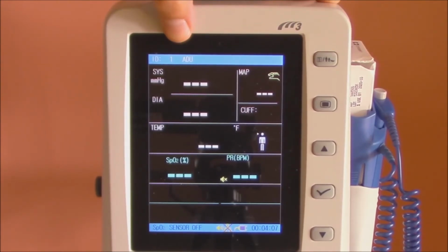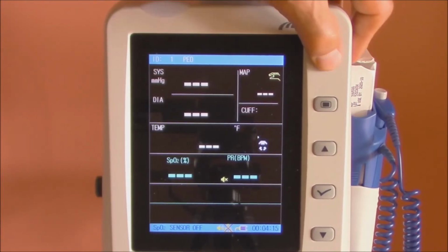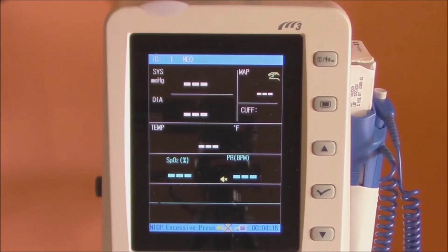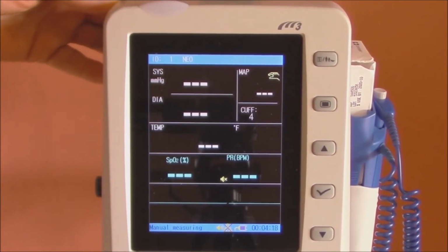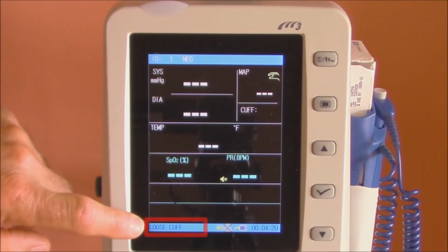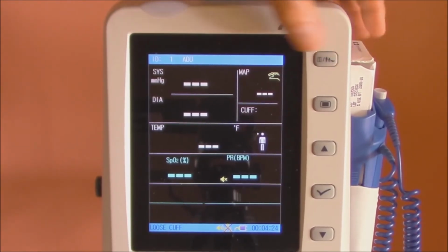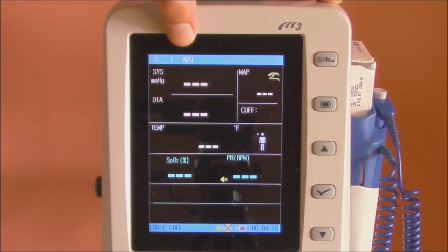Please note that for the Medline CareConnection deployments, the patient size must be set to Adult. If Neonatal is selected, the system will not inflate the adult blood pressure cuffs as a safety feature and will post a loose cuff error message. Should this error happen, simply keep pressing the patient size button until ADU for Adult appears on the blue status bar.